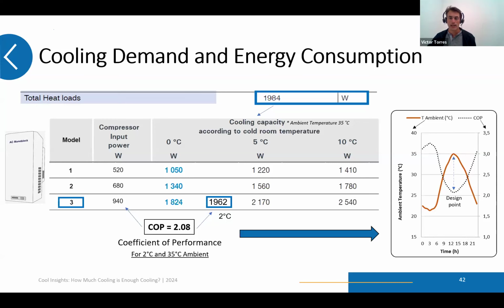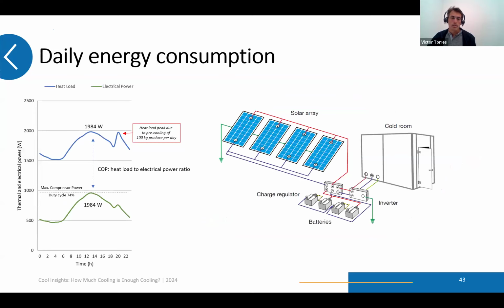In the next slide, I would like to drive you through the typical cooling demand profile that you will find. This is what you see here. This is the cooling demand. You see we have the maximum value of 1900 watts, and then, divided by the COP that is also changing based on the ambient temperature, you get a profile for your energy consumption. This is the electrical power that you are consuming. It goes from 500 watts to 1000 watts. So the duty cycle of our compressor will be around 74%. It means it will be working 74% of the time.